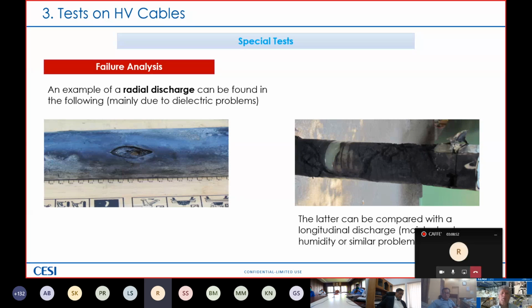I put here two examples of discharge. The one on the left is an example of a radial discharge. Radial because the flashover went from the shield, that is just under the sheath, directly towards the conductor. So this is a radial one, and it is an example mainly due to electrical problems. Vice versa, on the right side, you have a longitudinal discharge. That means that this path is along the length of the cable. That is mainly due to humidity penetration, or similar chemical penetration of this kind.